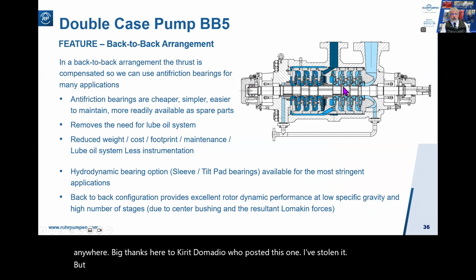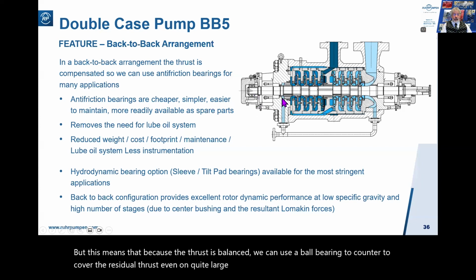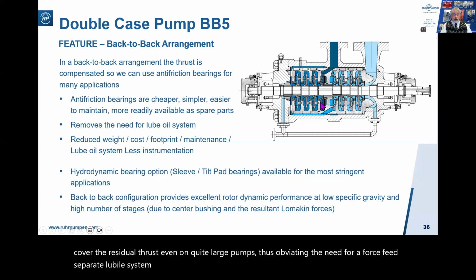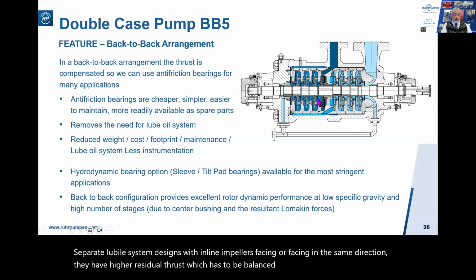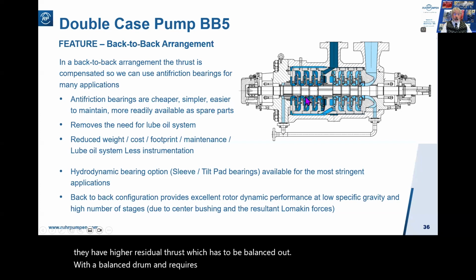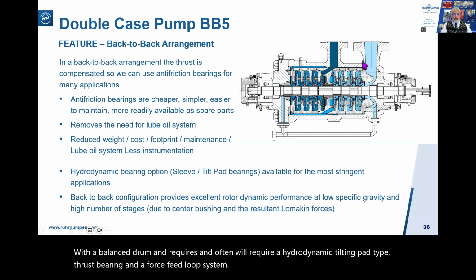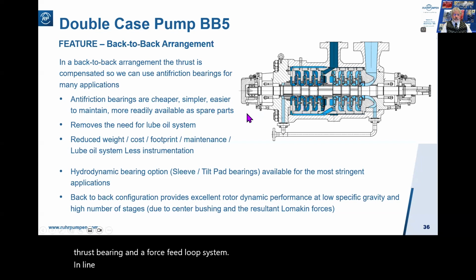Well, this means that because the thrust is balanced, we can use a ball bearing to cover the residual thrust, even on quite large pumps, thus obviating the need for a force feed separate lube oil system. Designs with inline impellers facing in the same direction have higher residual thrust, which has to be balanced out with a balance drum and often will require a hydrodynamic tilting pad type thrust bearing and a force feed lube system. Inline impellers are most commonly seen on smaller pumps, where the thrusts are not so great.